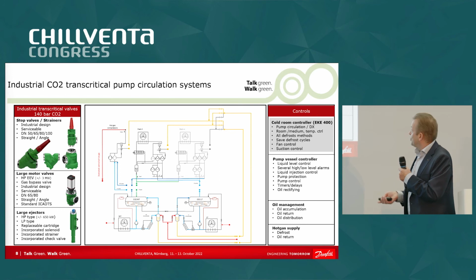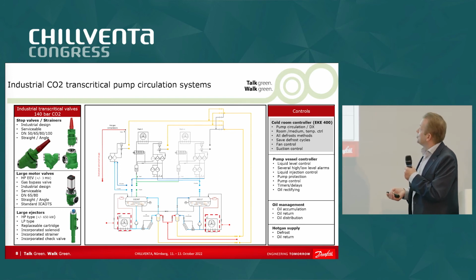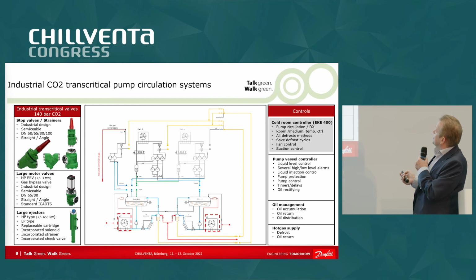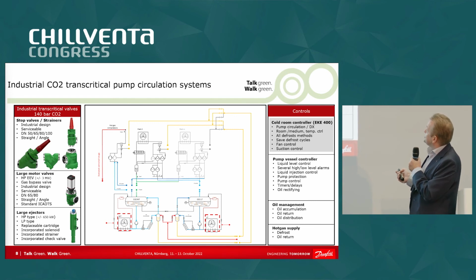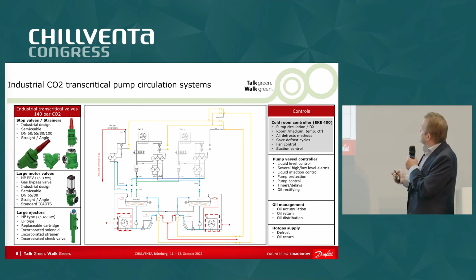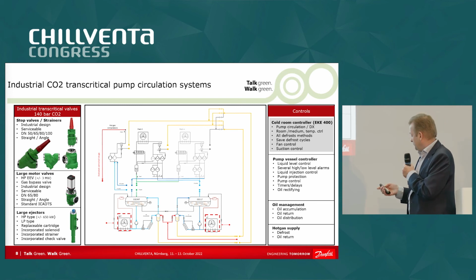But you also have to control all this system. That's what we're also working on. So we have controllers to control flooded systems, evaporators. That's the EKE 400. We can do pump circulation, we can do DX, we can control the room or the medium temperature. We can do all kind of defrost, fan control, suction control. So it's a complete industrial controller that we already have for such systems, both for ammonia and CO2.